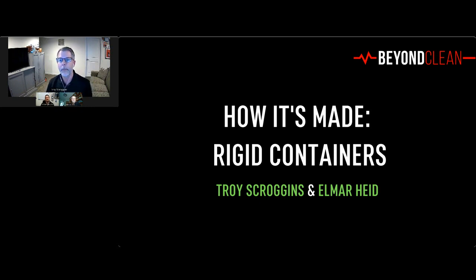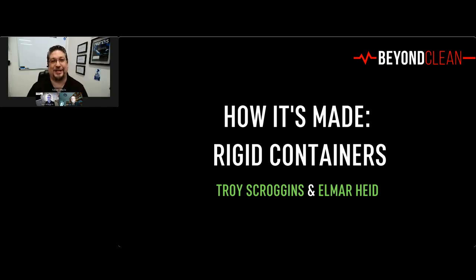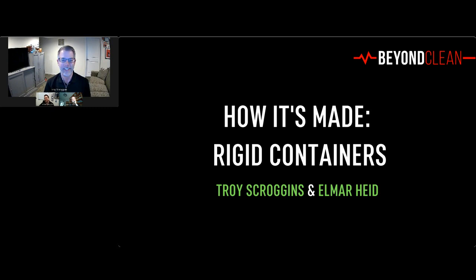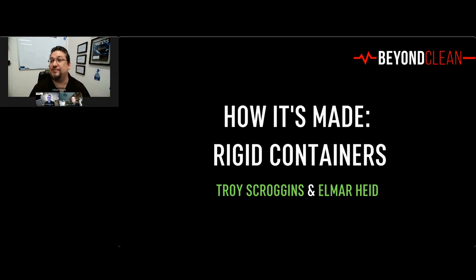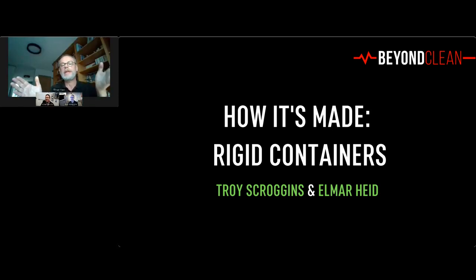Right. As a consultant, I've gone into hospitals and they say, our containers are really hard to get the lids to fit, and we're always sending them out for repair. Then I observe them, and they're throwing them onto the washer and dumping them on the cart washer rack. You have to treat it like an expensive piece of metal that can break if you mistreat it. If you mistreat those containers, they will bend and have issues. But if you treat them a little bit more carefully, they will have an extended life. Just remember they're a Class 2 medical device, just like all the other Class 2 medical devices we have in the department. It's the same with all types of packaging materials. If it's a peel pouch or a wrap, if you smash it on the table, you will have an issue.